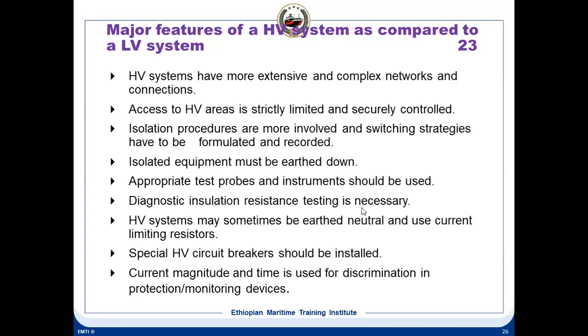Diagnostic insulation resistance testing is necessary. Insulation resistance has to be checked. High voltage systems may be earthed in neutral and use current limiting resistors. They are using NER. In all high voltage ships, the neutral is grounded through the NER, the neutral earthing resistor.